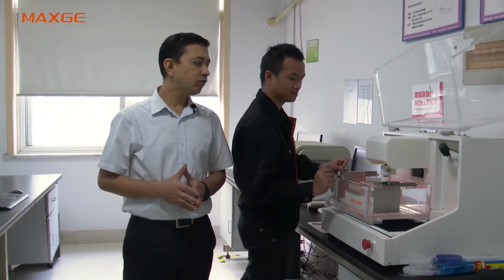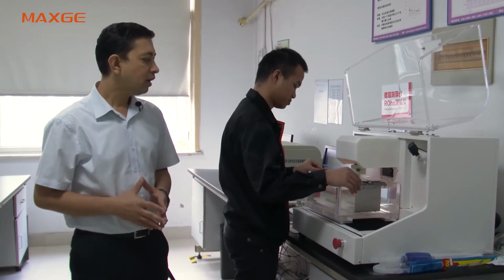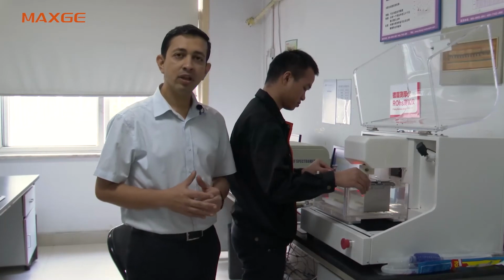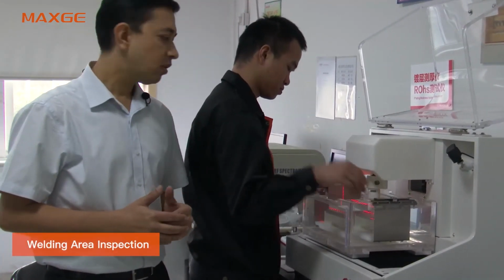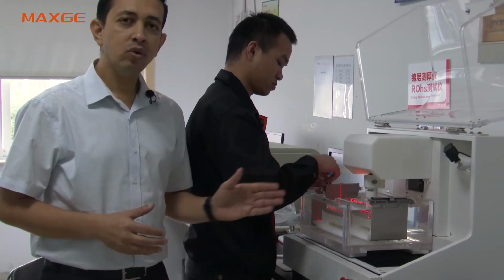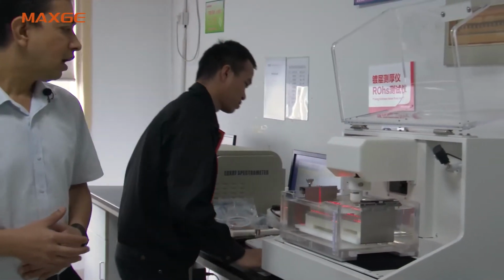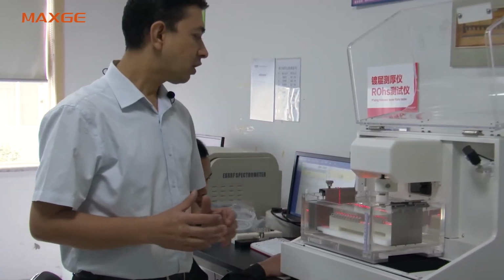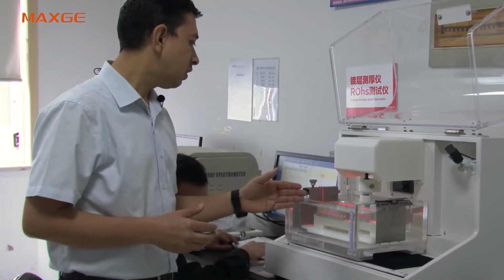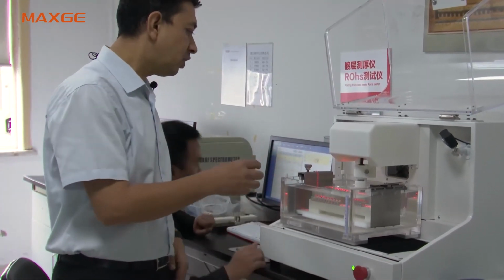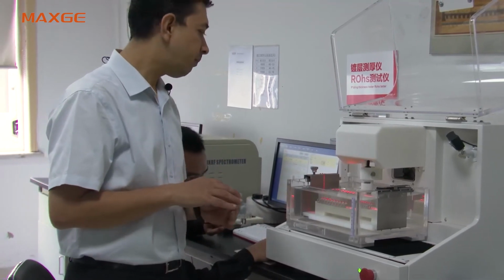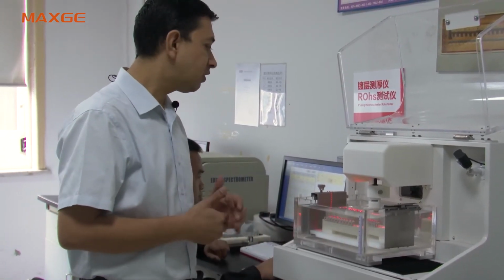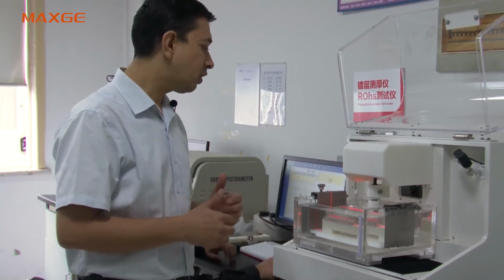Here I will introduce you to the first machine in the mechanical test laboratory. This is to check the welding strength of the contacts. As I told you, we have the automatic spot welding machines in our welding workshop. All the components come here for checking, and here you can see it will check the percentage of bonding of the silver button, with respect to how much it has been bonded. So without destroying the components, we can ensure that the bonding strength is there, and once we have good bonding strength, it finally results in good electrical endurance properties.